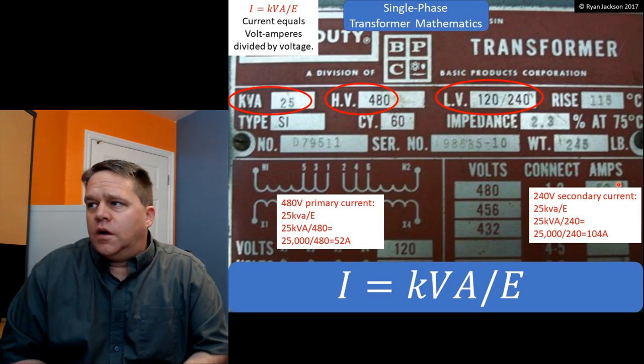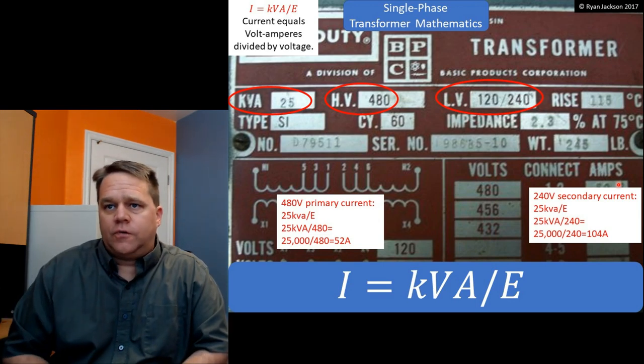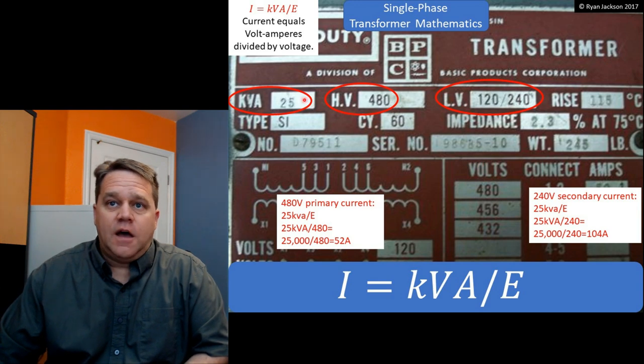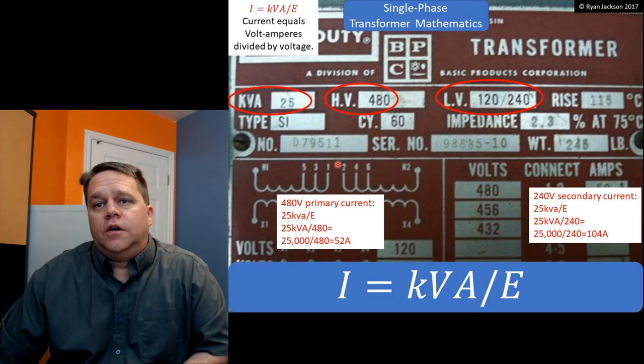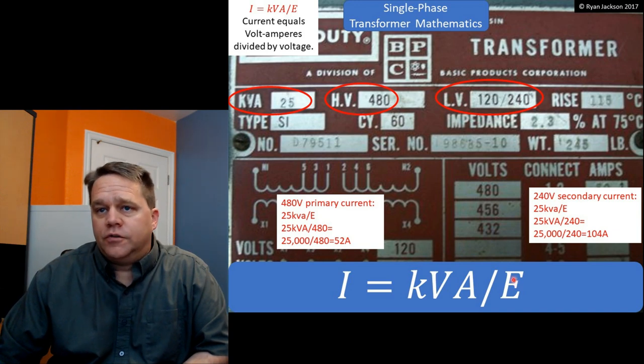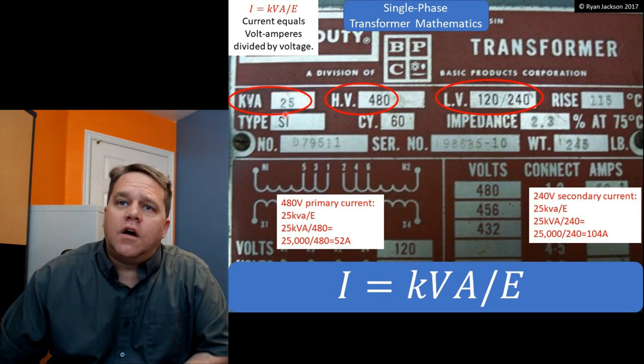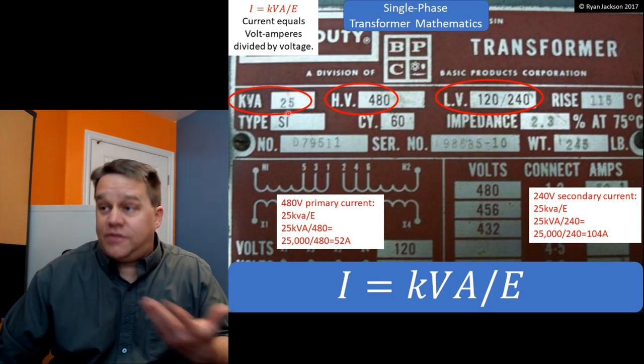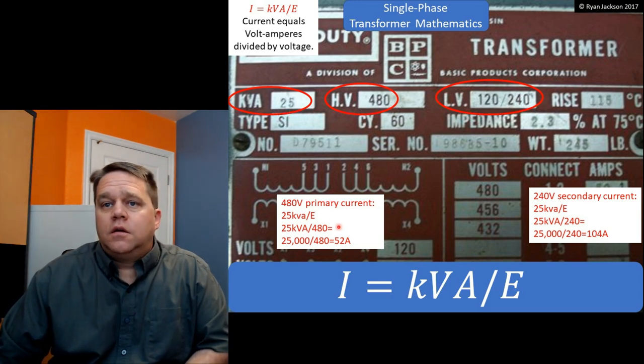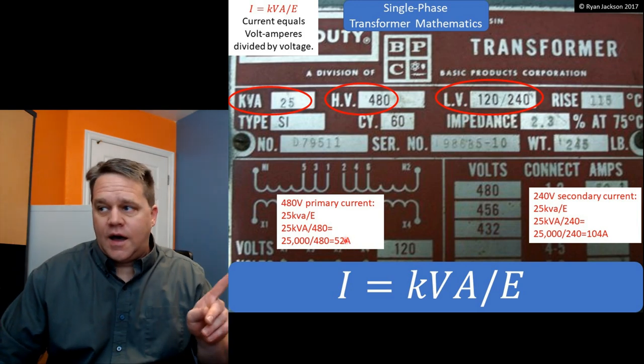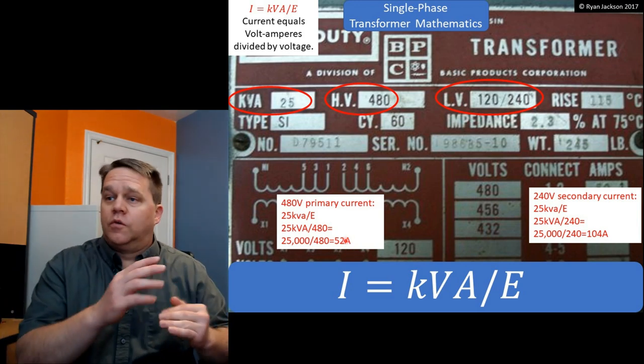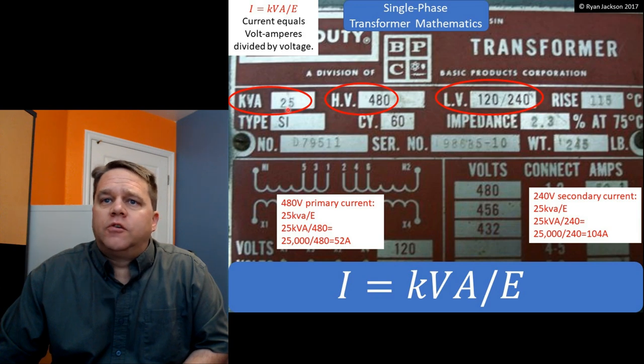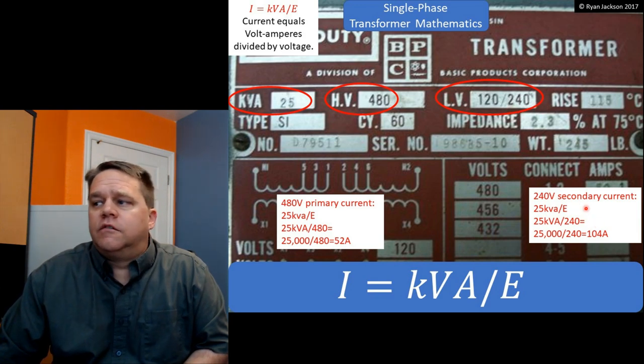First, transformer mathematics. Transformers don't have a current rating per se — they have a power rating in kVA. Current equals kVA divided by voltage: I = kVA / E. For a 25 kVA transformer with a high-voltage side of 480, take 25,000 volt-amps divided by 480 — that gives 52 amps on that side. If the secondary is at 240, then 25,000 divided by 240 gives 104 amps.